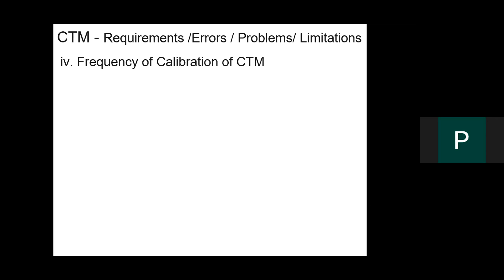Now I will give the exact calculation. Twice a year is perfect, provided there is no change in your system, no opening, no maintenance of any part related with the machine. If I'm opening my hydraulic machine, I have to do the calibration. If I am touching the panel, I have to do my calibration. If there is a variation, if I'm opening the analog dial, I have to check my calibration systems.